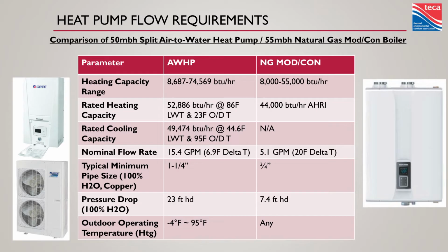Lastly, supply temperature range. Both start at about 77 Fahrenheit. We can do a lot of heating at 77 Fahrenheit in hydronics. The boiler, all the way up to 194. Great job. If it's actually boiling, you're doing it wrong. Forget the name. But the heat pump, 131, max, downhill with a tailwind. It does not get any hotter than that. That's based on R410A, and that's just a limitation of that. So this has a real hard line in the sand of where it can work and where it can't.